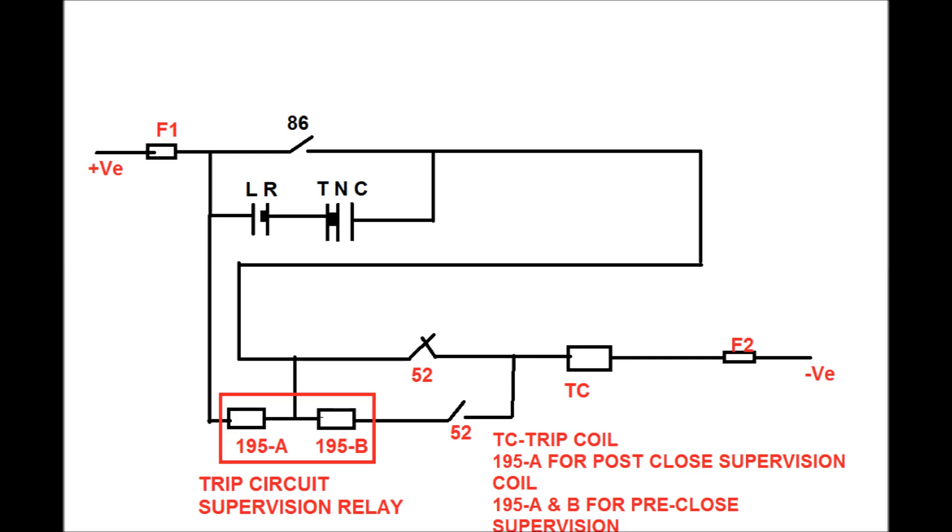For post-closed supervision only 195A will work and for pre-closed supervision relay both 195A and 195B will operate. The trip circuit supervision relay is already discussed in earlier video. Please check my video of TCS relay. TC is the trip coil.